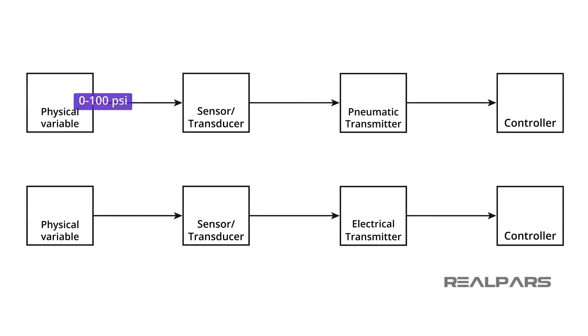In the early days of process control, the standard instrumentation signal was pneumatic, while today, it is more likely to be an electrical signal. The standard pneumatic signal is 3 to 15 psi. The standard electrical signals are 1 to 5 volts, or 4 to 20 milliamps.